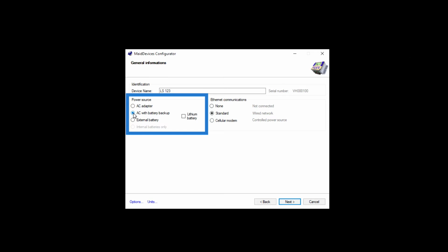The instrument will keep its battery charge. External battery means that the main power comes from rechargeable batteries, unless it is indicated that it is a non-rechargeable lithium battery. In this case, the instrument won't try to charge a battery, which could be dangerous.